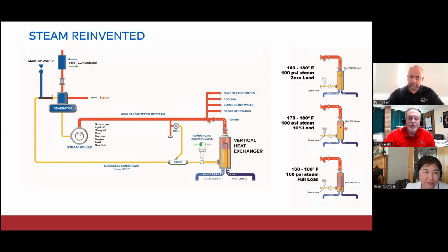Maxi-Therm received an innovation award for this from ASHRAE back in 2005, I believe, for basically making a variable area heat exchanger. Interesting concept. When we have to go full load, we will unflood the heat exchanger, but we always oversize our heat exchangers about 20% so that we always subcool condensate. We never deliver condensate out of our systems above 200 degrees Fahrenheit. We want to make sure that we don't flash.